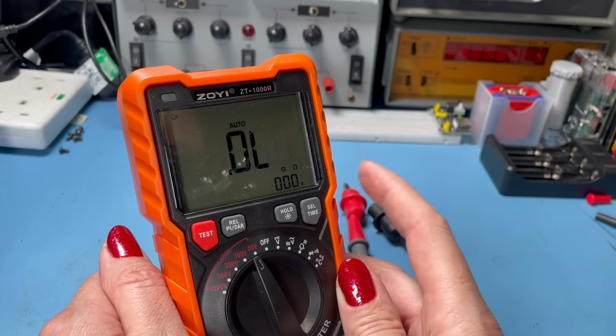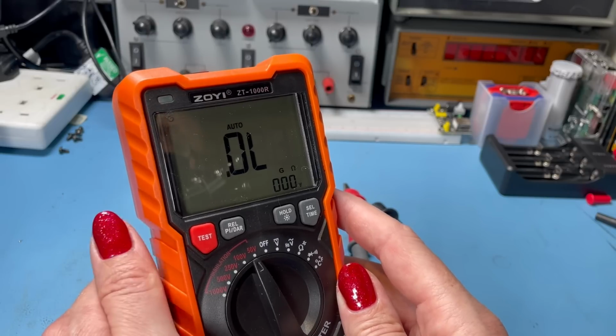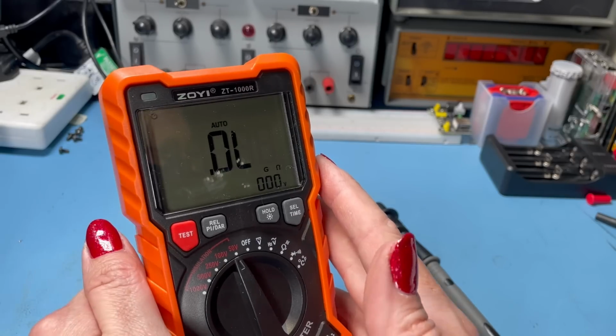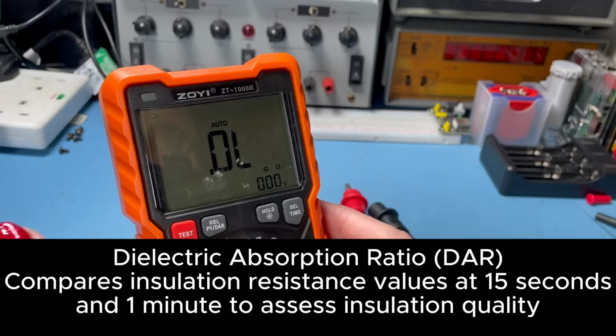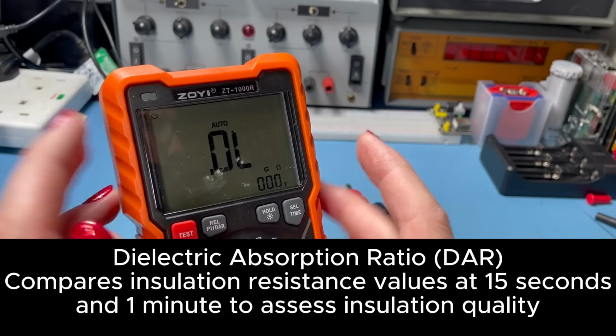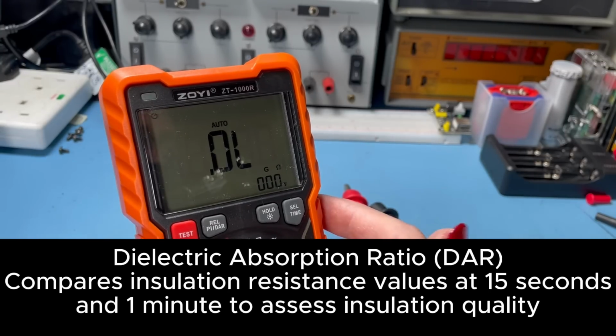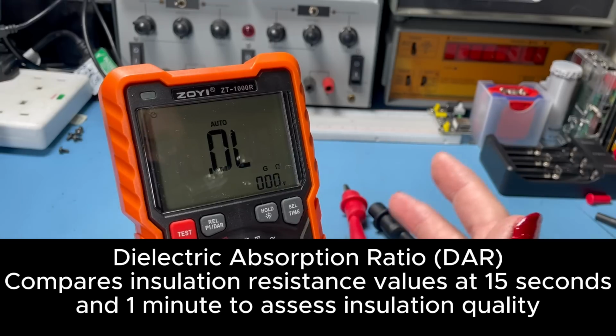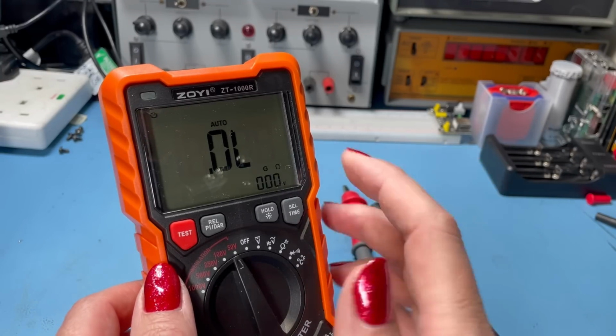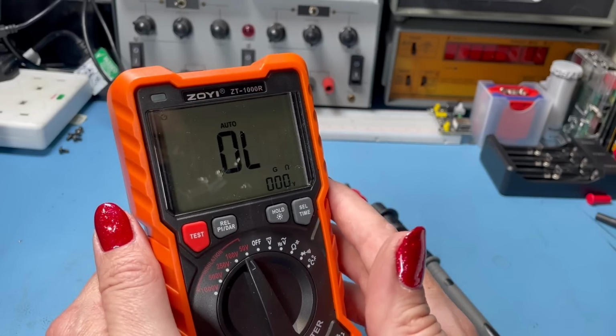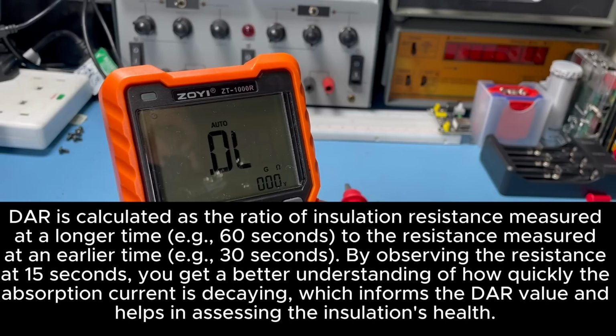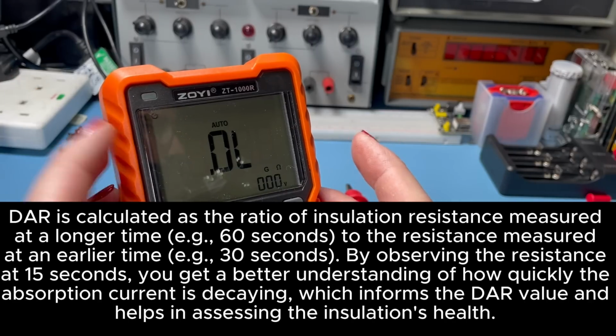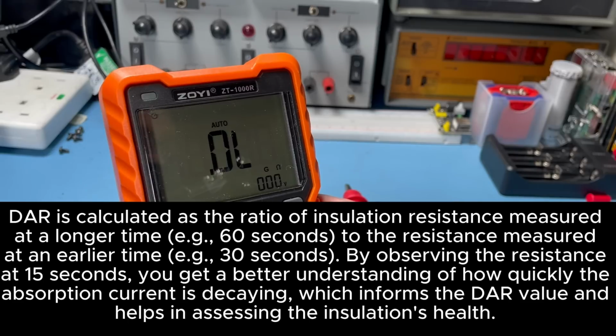You've got your DAR, which is your dielectric absorption ratio, and your PI, which is your polarization index. So the main difference between the two parameters is the DAR compares the insulation resistance values at 15 seconds and at 1 minute to assess the insulation quality. It takes two different readings. You might notice with some insulation meters like Fluke or Megger, they do this reading at 30 seconds and 1 minute, but with the Zoyi it does the reading at 15 seconds and 1 minute.